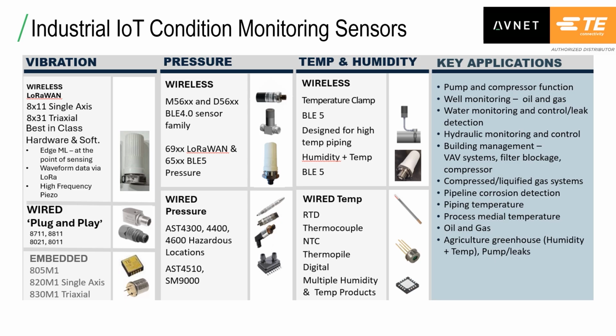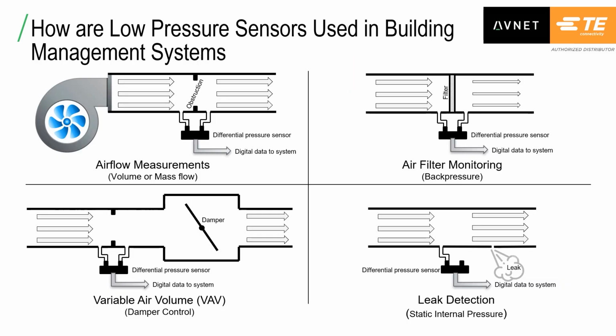Some of the key applications for condition monitoring are listed here and include everything from pump and compressor monitoring to building management applications. There are a wide range of building management and HVAC applications that require low or ultra-low pressure sensors to accurately monitor and control airflow in a building. Typical static pressure for commercial duct systems is around half an inch of water, or 0.02 psi, or 125 Pascal. Even lower pressures will be seen when looking at differential pressures, which is key in several of these applications.